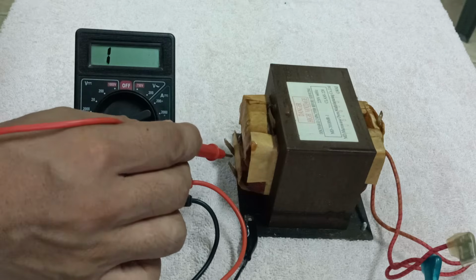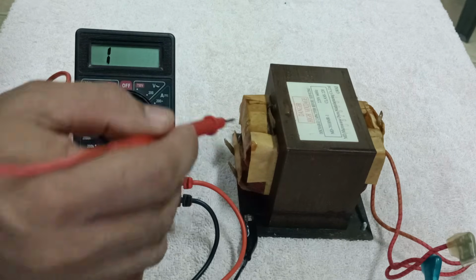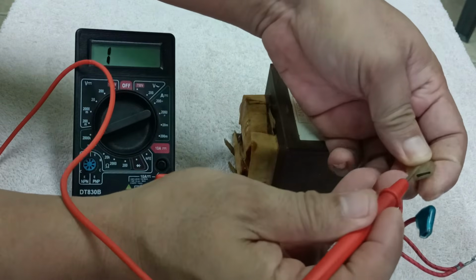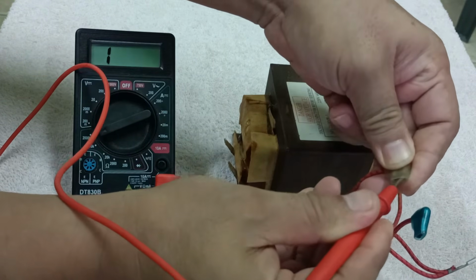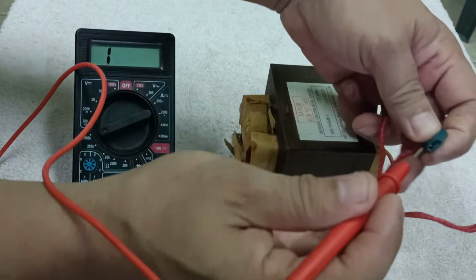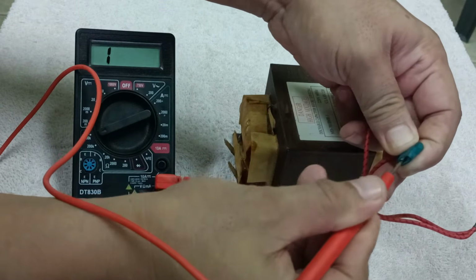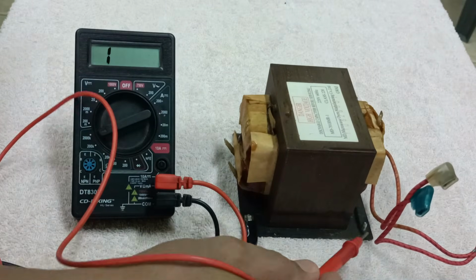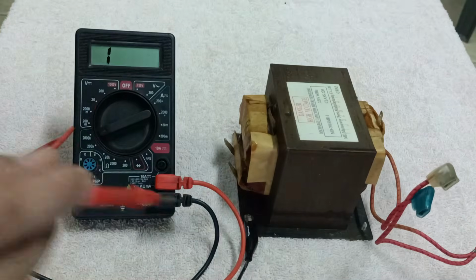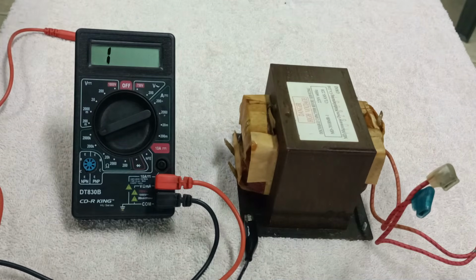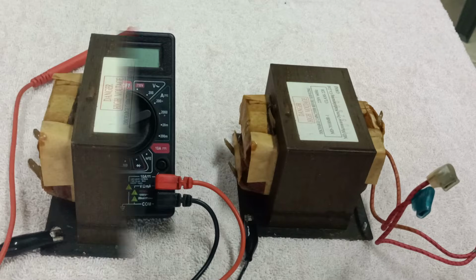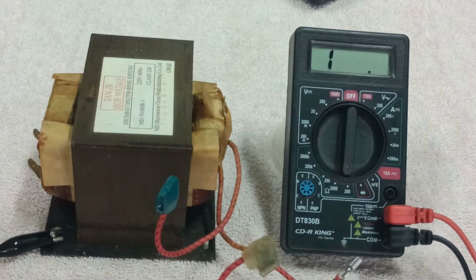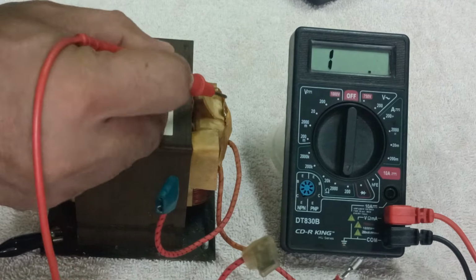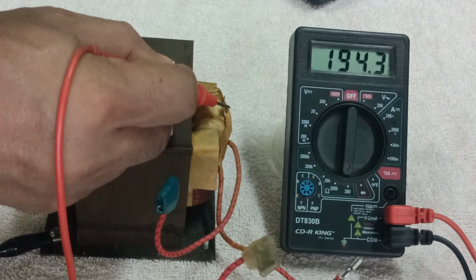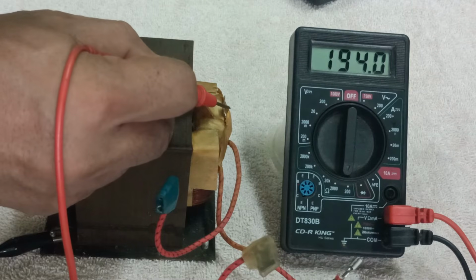Next, I check the primary terminals with respect to ground. Set the digital ohmmeter to 2000 K range. It shows an open circuit. This is a good test. Then I test the high voltage terminal with respect to ground. I get a resistance reading of about 200 ohms. This is also a good test.